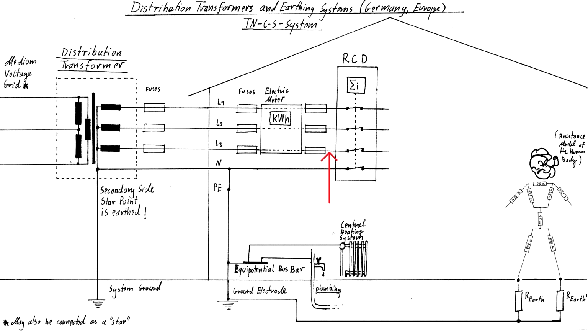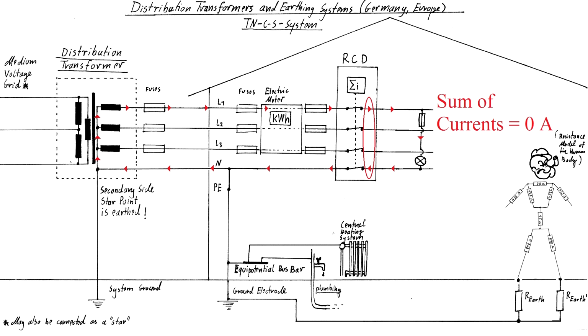But that's of course where the residual current device, or RCD, comes into play. First of all, what does the RCD do? For that, let us connect a single phase load like this light bulb between one of the phases and the neutral. The RCD is now measuring the overall sum of the currents through all 3 phases and the neutral conductor. Since all current that passes through the light bulb is returned over the neutral and through the RCD, the overall sum of the current is 0 amperes. Therefore, the RCD will do nothing.